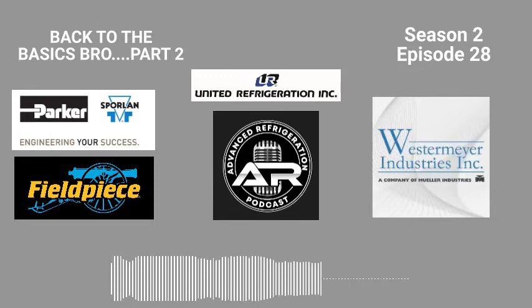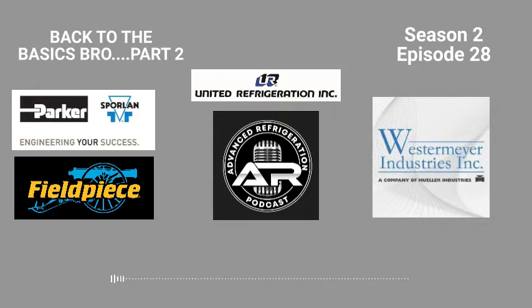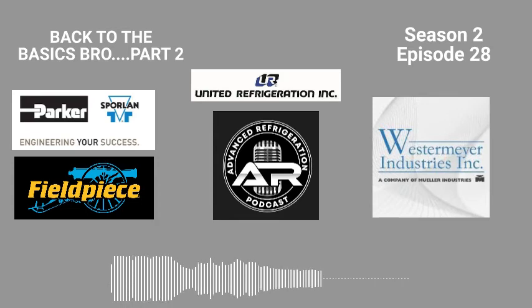Had he actually looked at the case objectively, he'd have seen, okay, the superheat's like nothing, but I'm not cooling because the equalizer line is frosted up and it's just blowing into the suction. One of the things about those Danfoss expansion valves, I don't know what it is, but if they're clamped down fairly low, where you're trying to maintain a higher superheat, I've seen where they start bypassing. As soon as I open it up and adjust it back to whatever superheat the case needs to be, it starts feeding fine.